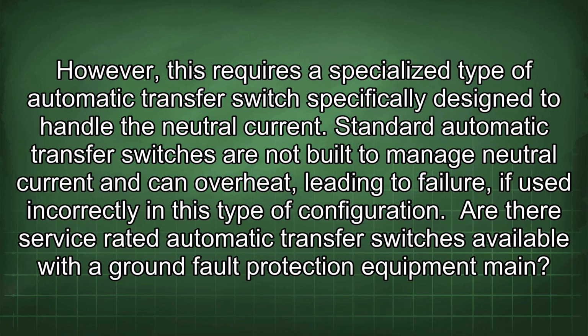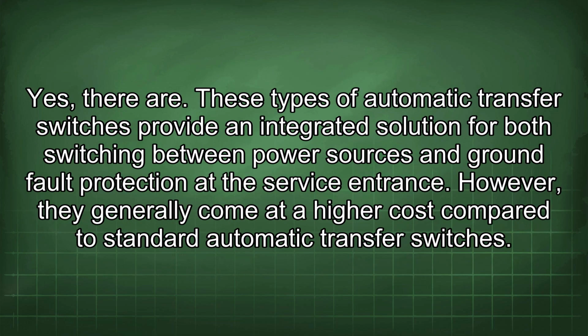Are there service-rated automatic transfer switches available with a ground fault protection equipment main? Yes, there are. These types of automatic transfer switches provide an integrated solution for both switching between power sources and ground fault protection at the service entrance. However, they generally come at a high cost compared to standard automatic transfer switches.